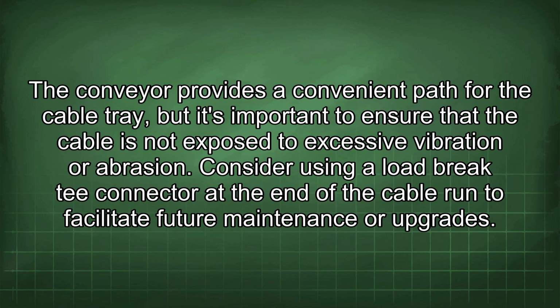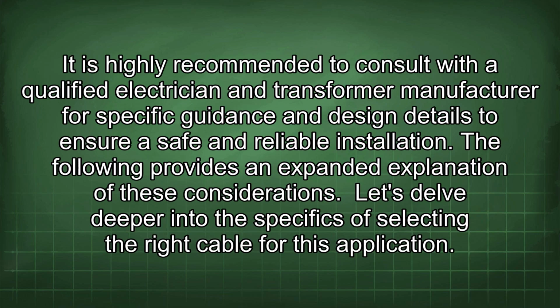The conveyor provides a convenient path for the cable tray, but it's important to ensure that the cable is not exposed to excessive vibration or abrasion. Consider using a load break T-connector at the end of the cable run to facilitate future maintenance or upgrades. It is highly recommended to consult with a qualified electrician and transformer manufacturer for specific guidance and design details to ensure a safe and reliable installation. The following provides an expanded explanation of these considerations.